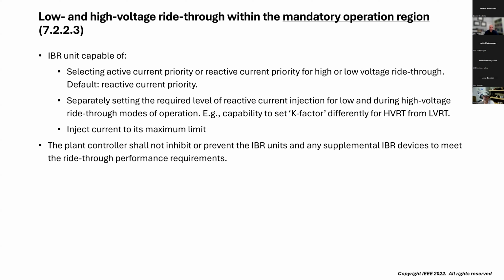An easy example to think about is if they use a K factor type proportional control for voltage deviation, you may want to set that. The IBR unit needs the capability to set that differently for HVRT, high voltage ride through, versus low voltage ride through.